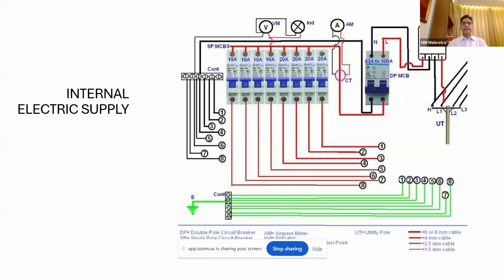Now here you can see for 8 circuits, there are 8 phase wires, 8 neutral wires, and 8 earth wires also. So this is a check. Suppose you go to site and you find the number of any of the wires is less here. Suppose somebody has looped the earth wire or neutral wire somewhere on the way while the building work is proceeding. If it is not coming to my distribution board, the number of wires connected here will be less. So you have to take care of that.